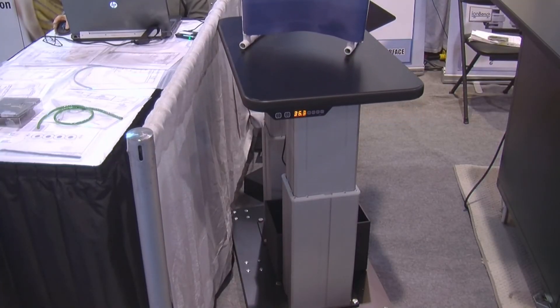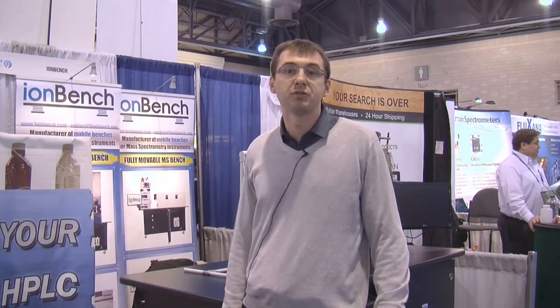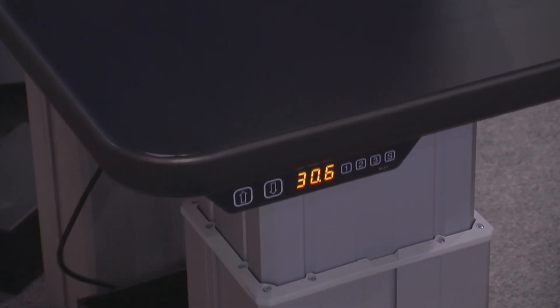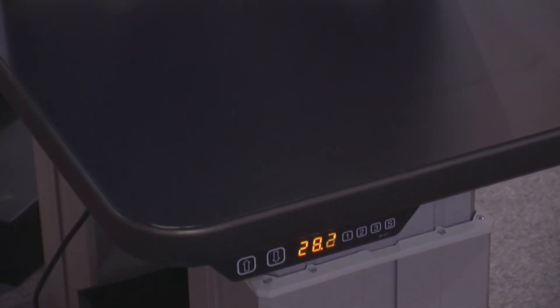The second product line is the elevating table for liquid chromatography. The main advantage is that it is electronically liftable, making it easy and safe to access the solvents, because most HPLCs on the market are very high-stacked — more than 6 feet. You can easily move the LC in the lab to connect it from one mass spec to another. You can also memorize positions so you can replicate the same height for certain applications, especially for capillary electrophoresis, where it is possible to adjust very precisely the height of the LC cart to the mass spec inlet.